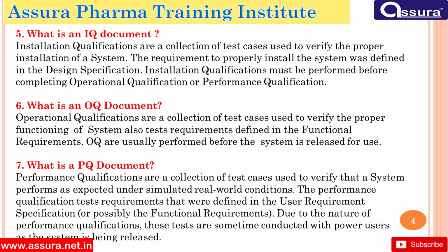What is an IQ document? Installation qualification is a collection of test cases used to verify the proper installation of a system. The requirements to properly install the system were defined in the design specification. Installation qualifications must be performed before completing operational qualification and performance qualification.